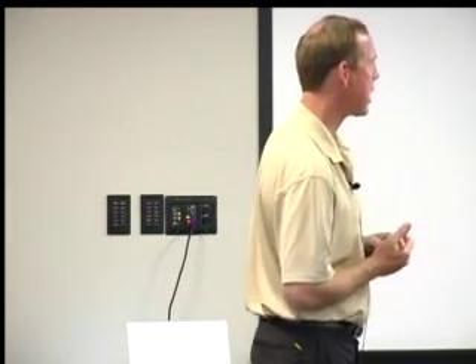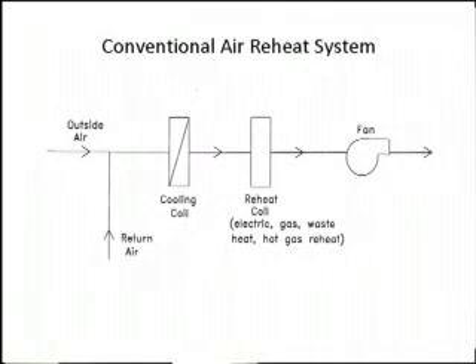So first, a little schematic of how it works. Again, we're mixing outside air and return air, so we've got a mixture of air and water vapor here. We're condensing a lot of it out, but we come off this coil in the low 50s again, and our space is simply not producing enough heat to keep the balance, right? So it's overcooling, so we have to turn on some kind of reheat. And this can be done with electric, like we saw on the last slide. It can also be done with hot water if we have a source for hot water, and some people do have some waste stream for hot water.